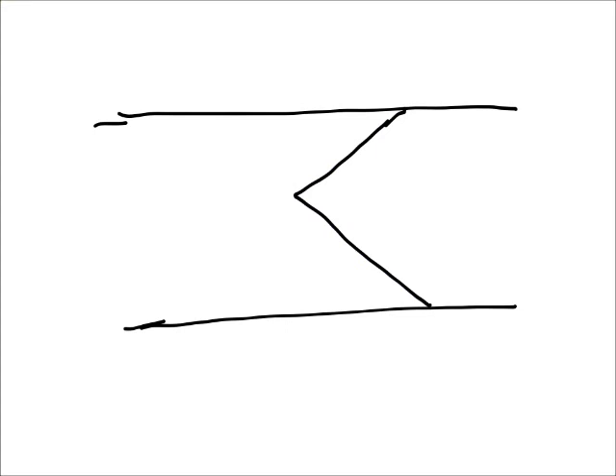Here is my sketch of the expiratory valve. Expiratory flow comes out and here is the valve, highlighted in orange. There is a difference between a closed valve and a controlled valve. During volume control ventilation, it closes during the inspiratory phase based on time, as already discussed. However, during pressure control ventilation, it is a controlled expiratory valve.